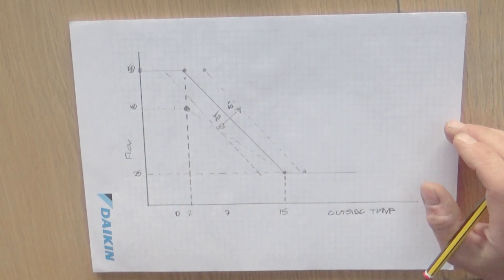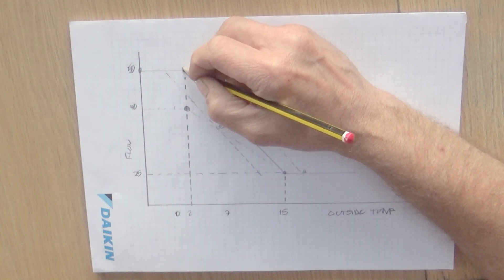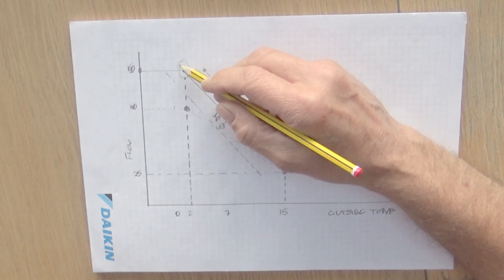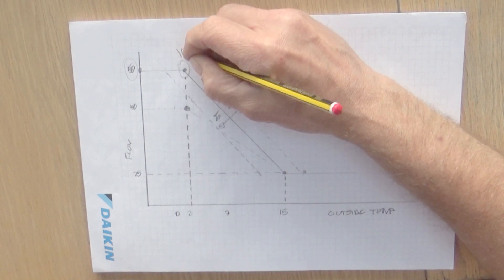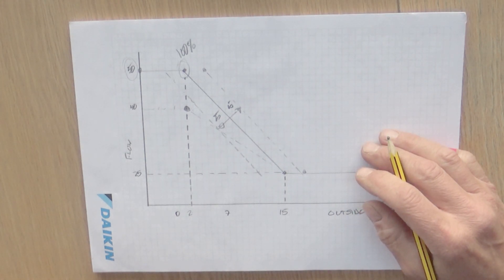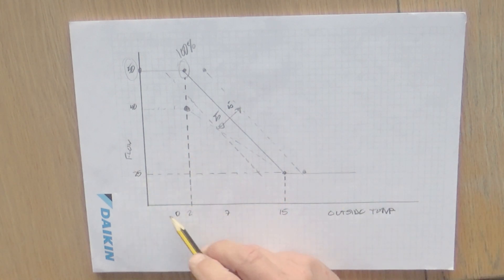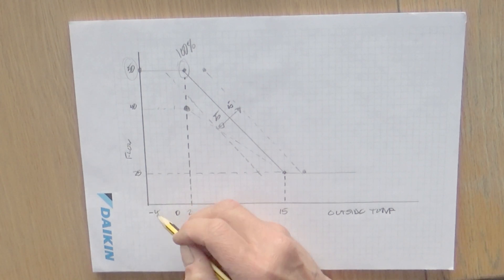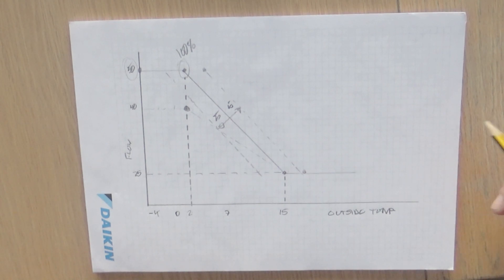If people want it warmer, they can shift the whole line by five or a couple of degrees. If they want it cooler, they can shift it back. That gives a little bit of controllability in the early winter months. The design criteria might be two degrees outside and you want your heating system to be 50 degrees — that's your 100% load, where you're guaranteeing to keep your customer warm. And obviously in Scotland, the design point could be minus two, minus four or beyond. That's how we'd base our radiators or underfloor heating systems.